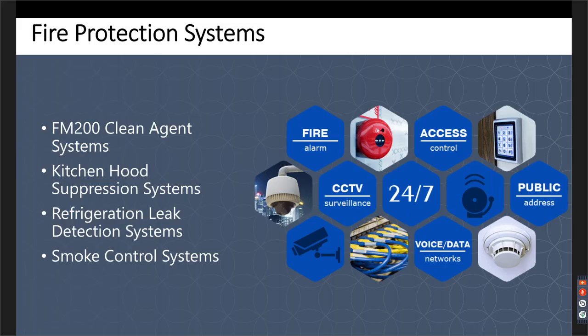And then just to kind of bring it all home, there are other types of fire suppression systems that you may have in these various different types of clinics. Some are going to be more prevalent than others. Clean agent systems for IDF rooms and computer rooms. Kitchen hood suppression systems if you have commercial cooking in your particular clinic. Refrigeration machine rooms may require refrigerant leak detection systems. Some of these buildings may require mechanical smoke control systems if you have atriums, for instance, or high-rise buildings. So fire alarm is not the only fire protection system, there are all of these others as well.